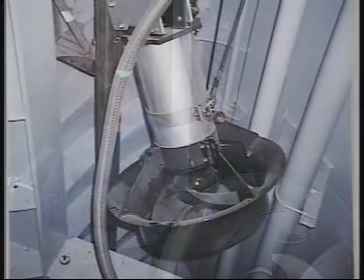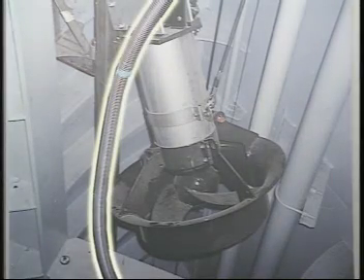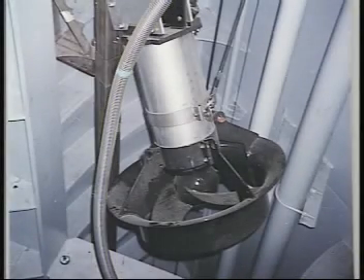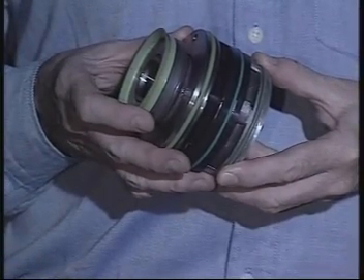However, the temperature must be lower than 70 degrees Celsius or 160 Fahrenheit, and the need for chemical resistance must be moderate. For instance, the SUBCAB can't be used in oil-based mud unless it's protected with a certain steel shielding. And in abrasive environments, or when cleaning chemicals are used, cable protection such as the Flygt metal hose or its equivalent is recommended. The Flygt plug-in seal with tungsten carbide seal rings is the recommended seal type for most applications.